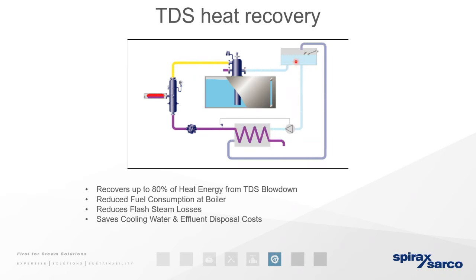So you're heating this water. We then have the flash recovery, the differential of pressure that's coming through here, and that's being fed into a de-aerator unit in this particular case. We're trying to capture as much energy from that TDS, because remember that's at 10 bar temperature, so it contains the energy that you would normally be using to make steam. We don't want to just send that to drain and waste it. A good way, as we said here, is the heat exchanger, so it reduces the loss. The hotter your water, the less fuel you need to raise the temperature and so on.